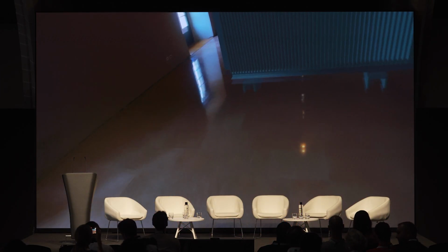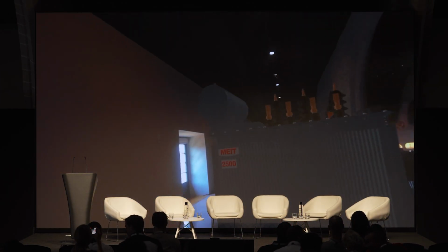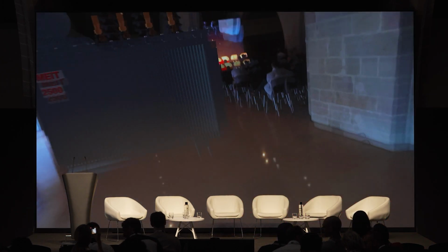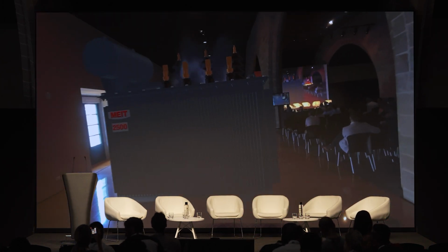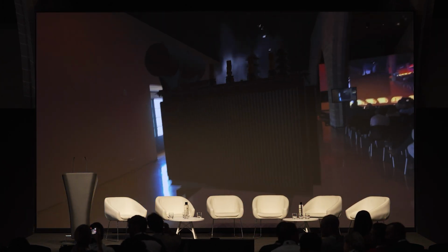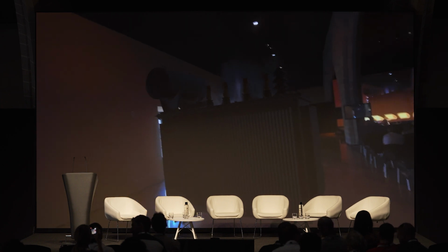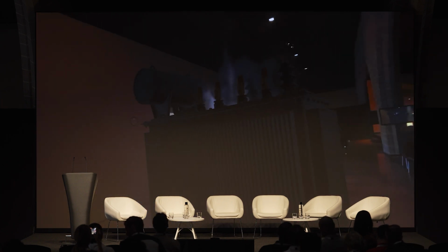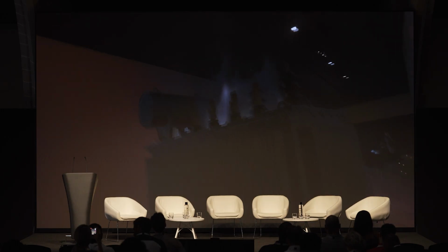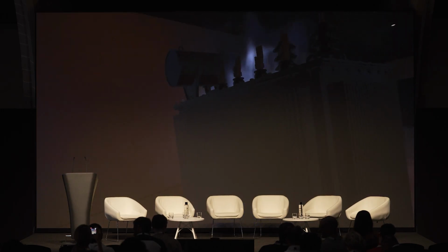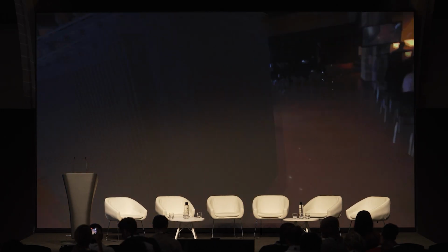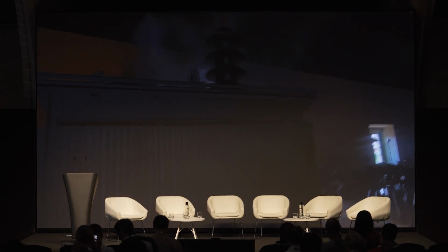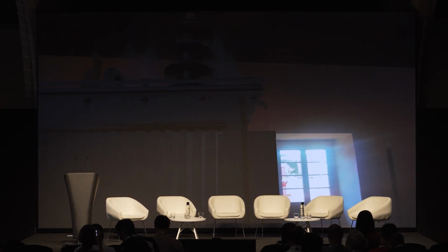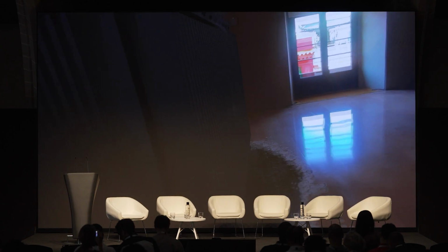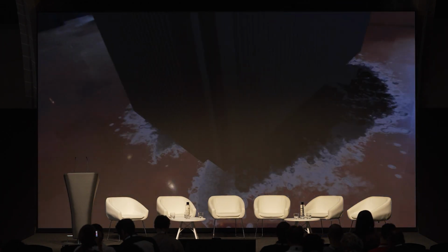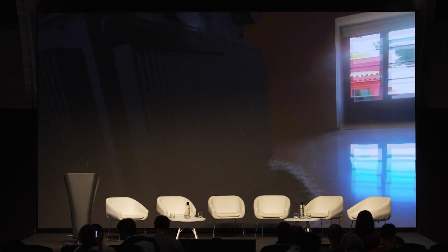You are now observing a pad-mounted transformer operating under nominal load. However, unnoticed overloading during peak hours has accelerated insulation deterioration and increased moisture ingress inside the tank. Over time, that will cause an insulation breakdown inside of it, and partial discharges develop across the degraded paper oil insulation system. The arc vaporizes oil instantly, generating high-pressure gas and leading to tank rupture and external fire that will sooner cause an explosion of the transformer.